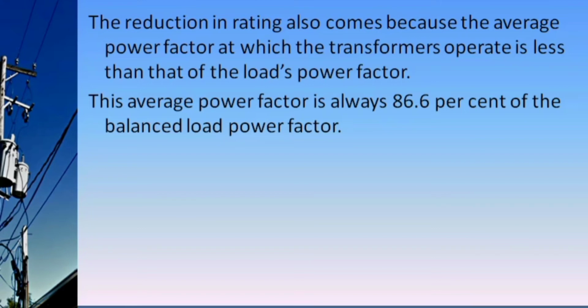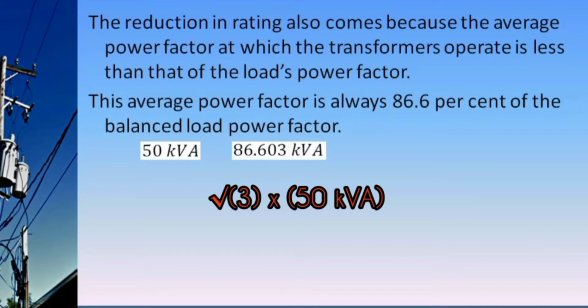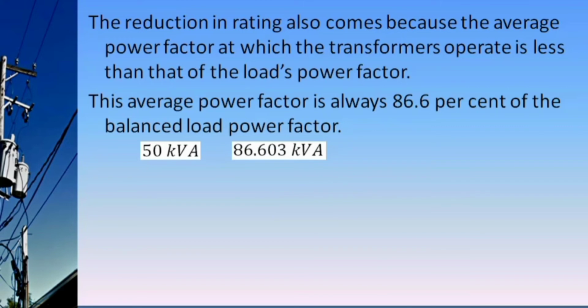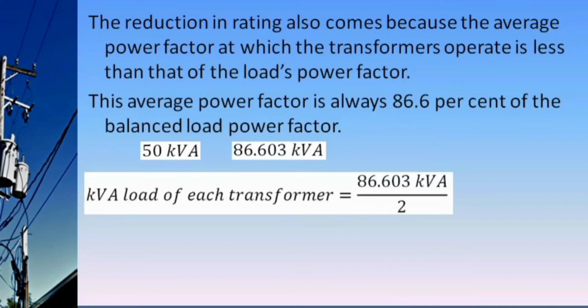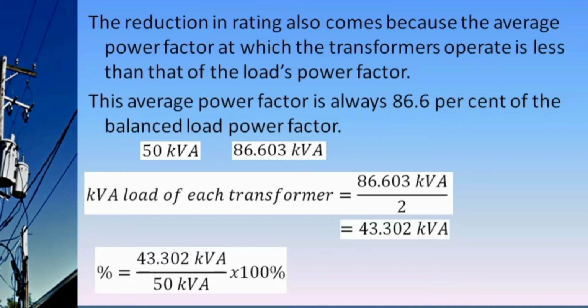Again, if each transformer of an open delta is rated 50 kVA, and we know that the system will give us 86.603 kVA from square root of 3 times 50 kVA, to determine the kVA load of each transformer, we divide this value by 2. So that is 86.603 kVA divided by 2, we have 43.302 kVA. To determine the percentage of this load from its rating, we have 43.302 kVA, divide this by 50 kVA times 100%, we have 86.604%. That's why it says the average power factor is always 86.6% of the balanced load power factor.